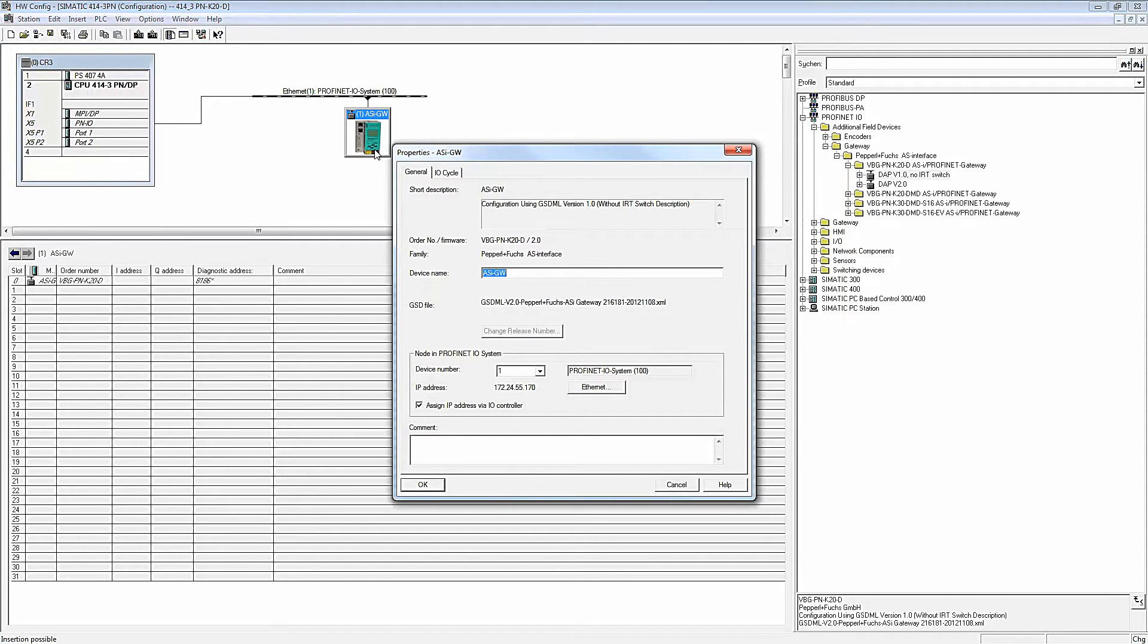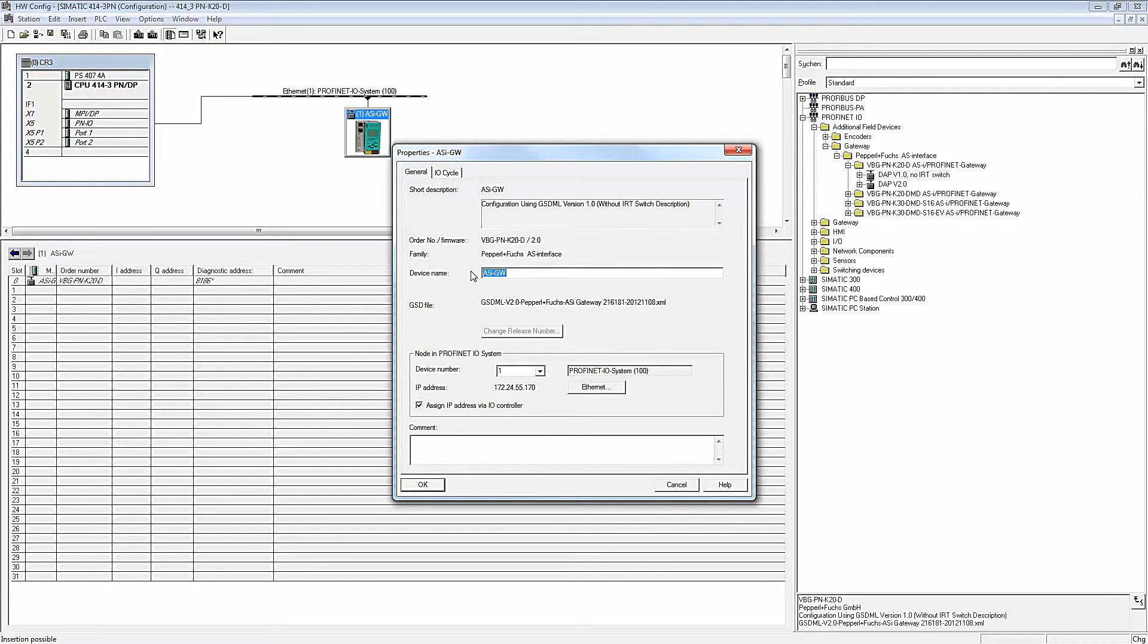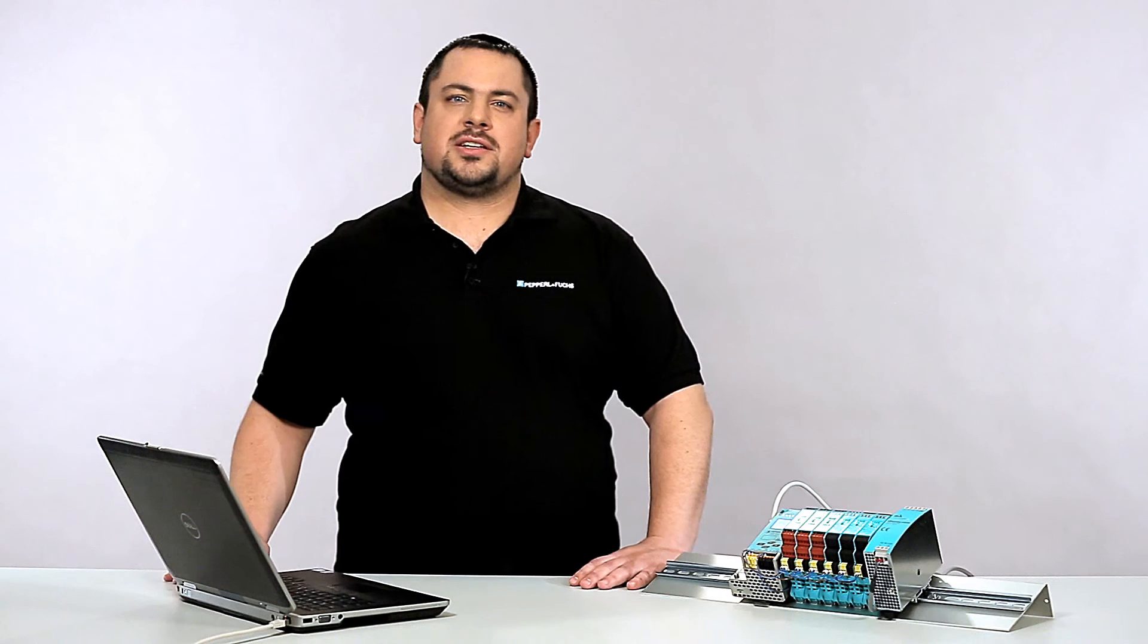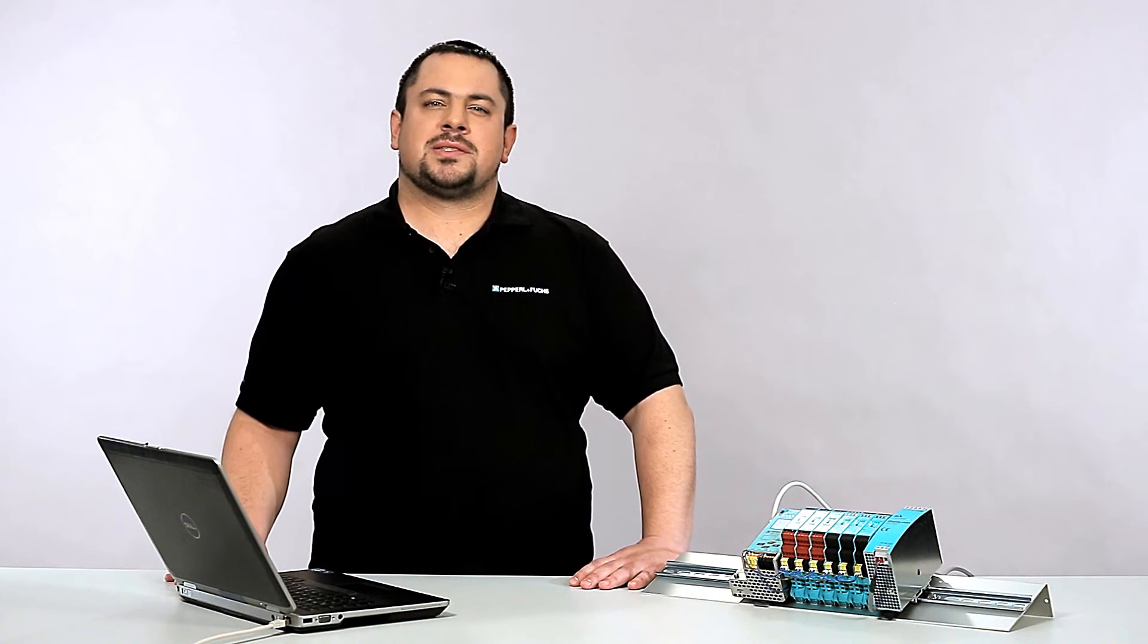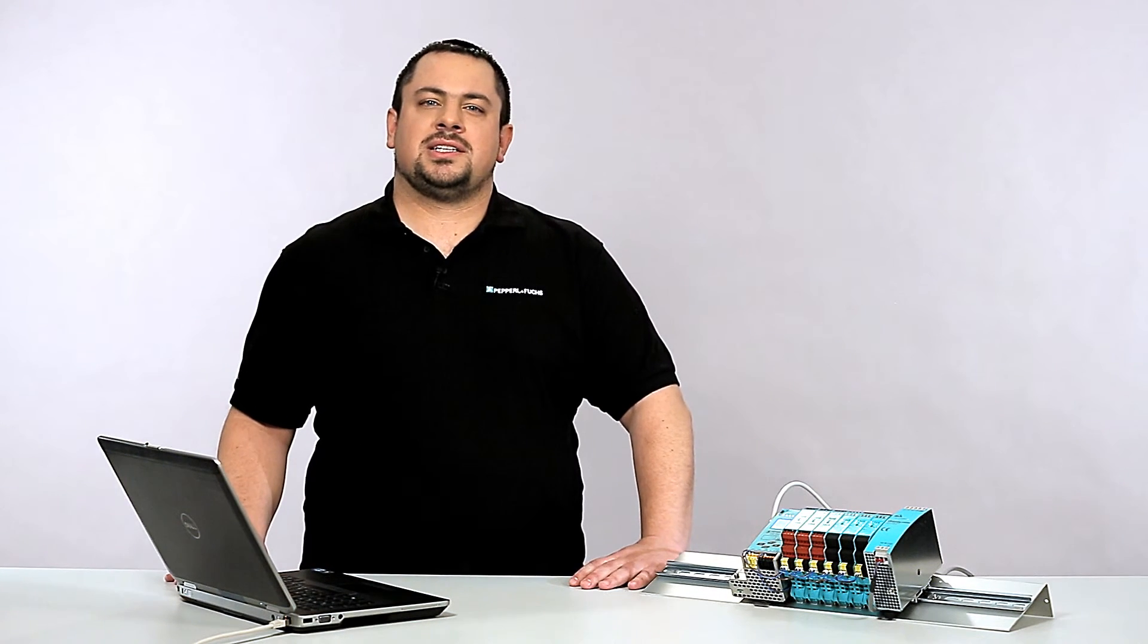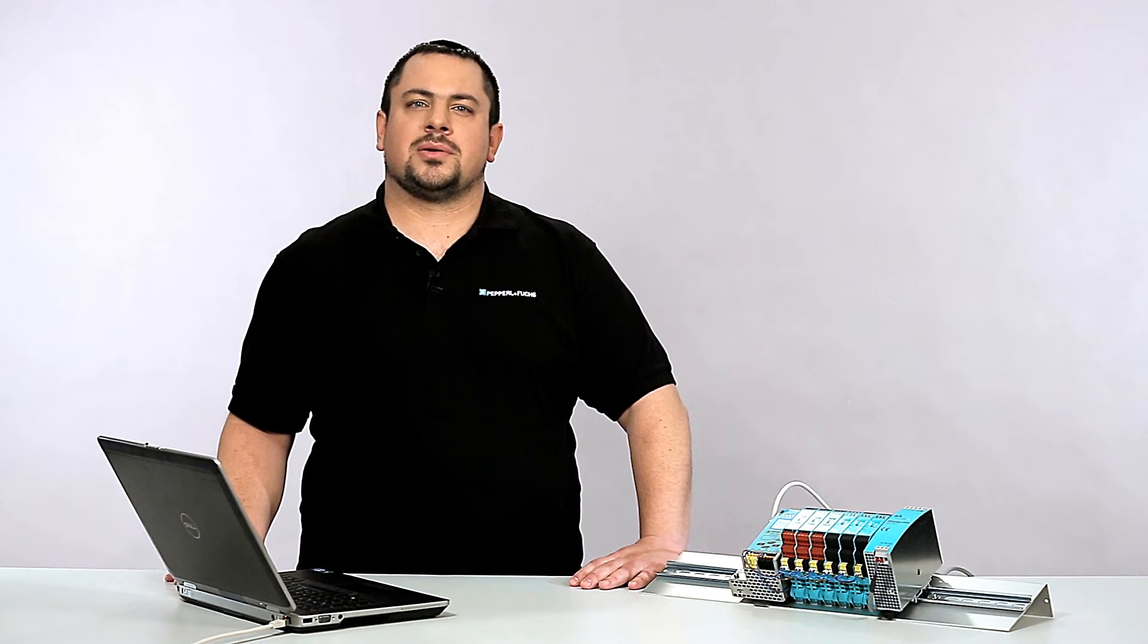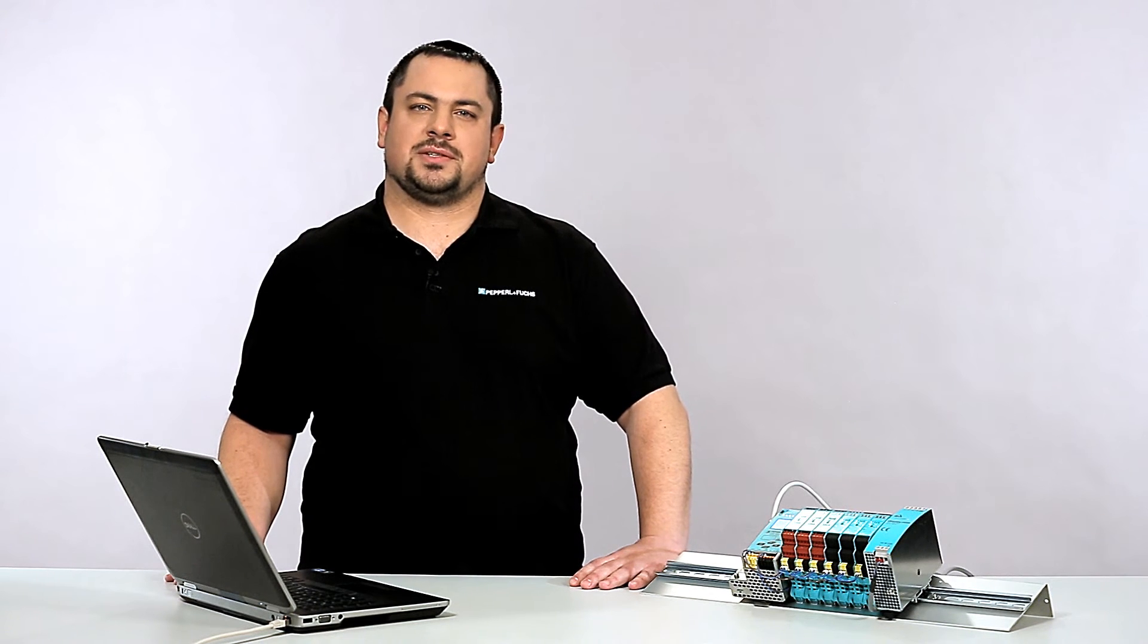Double-click on the Gateway icon to access object properties. You must assign a unique name for the device to ensure that the Profinet controller detects the right device. Make sure that the box Assign IP address via I/O controller stays checked, so that the IP address will be automatically assigned to the Gateway when downloading the configuration.